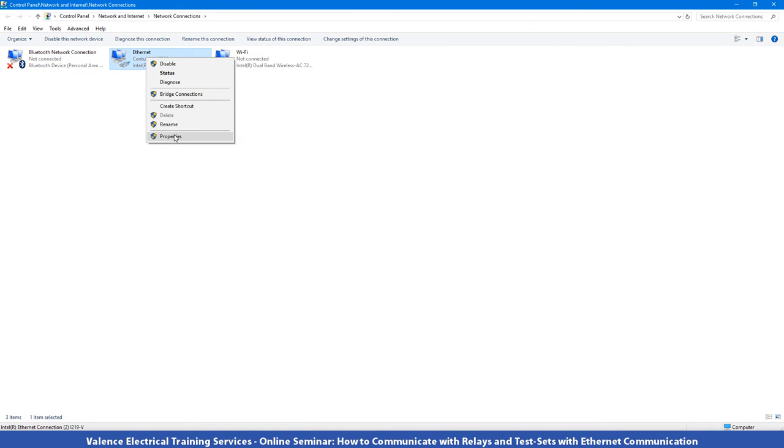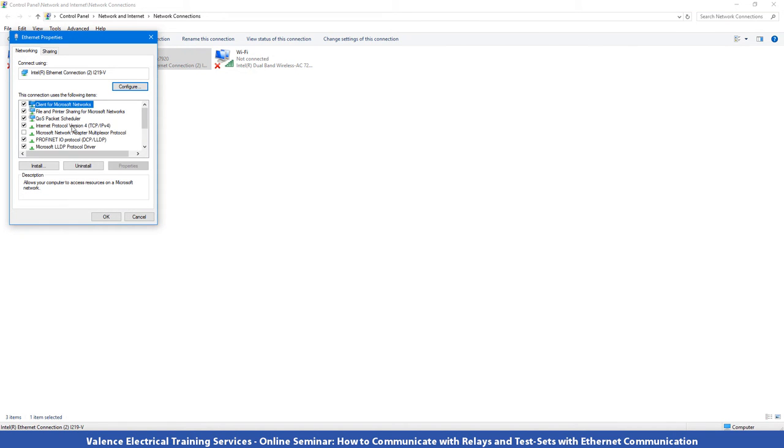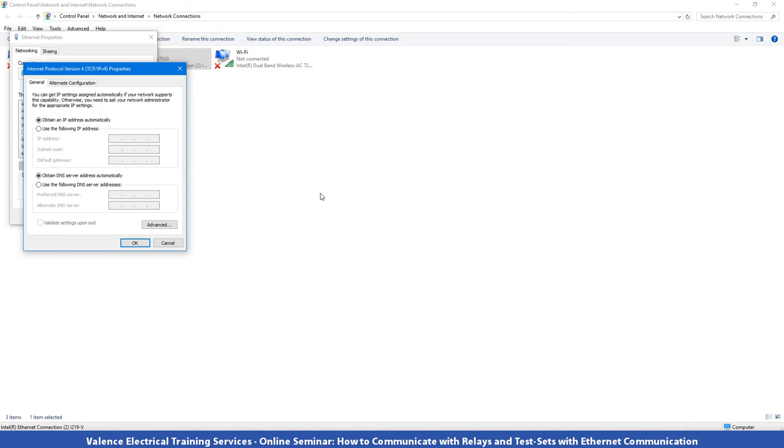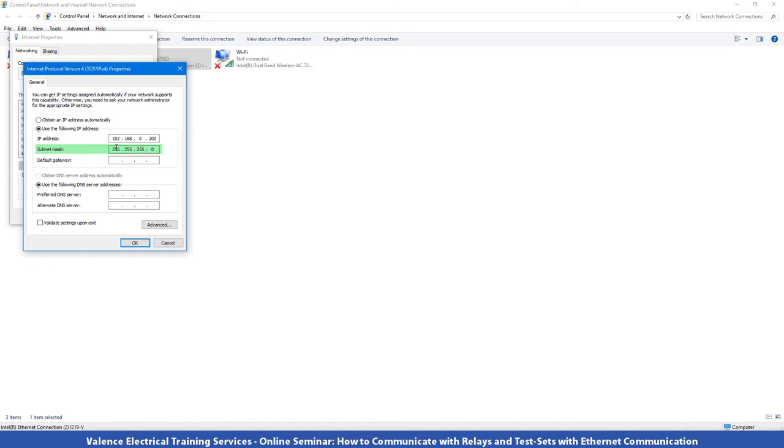Then you want to select internet protocol version 4 and hit properties again. And usually you'll see that the obtain IP address automatically is selected. But if you don't see that and this other one is selected, which is use the following IP address, you're going to want to write those numbers down because you're going to need that information if you want to talk to the hotel or the office internet connection when you leave the job site. Now I want to communicate with devices that have the same country code of 192 and then they have the same state code of 168 and they have the same city code of 0. And the devices I want to talk to are 250 and 253. So I don't want to be either of those numbers for this last one. So I'm going to type 200 and then you want to click in subnet mask and some numbers will automatically be populated. Subnet mask is not as important as the IP address and usually you don't have to think about it at all.